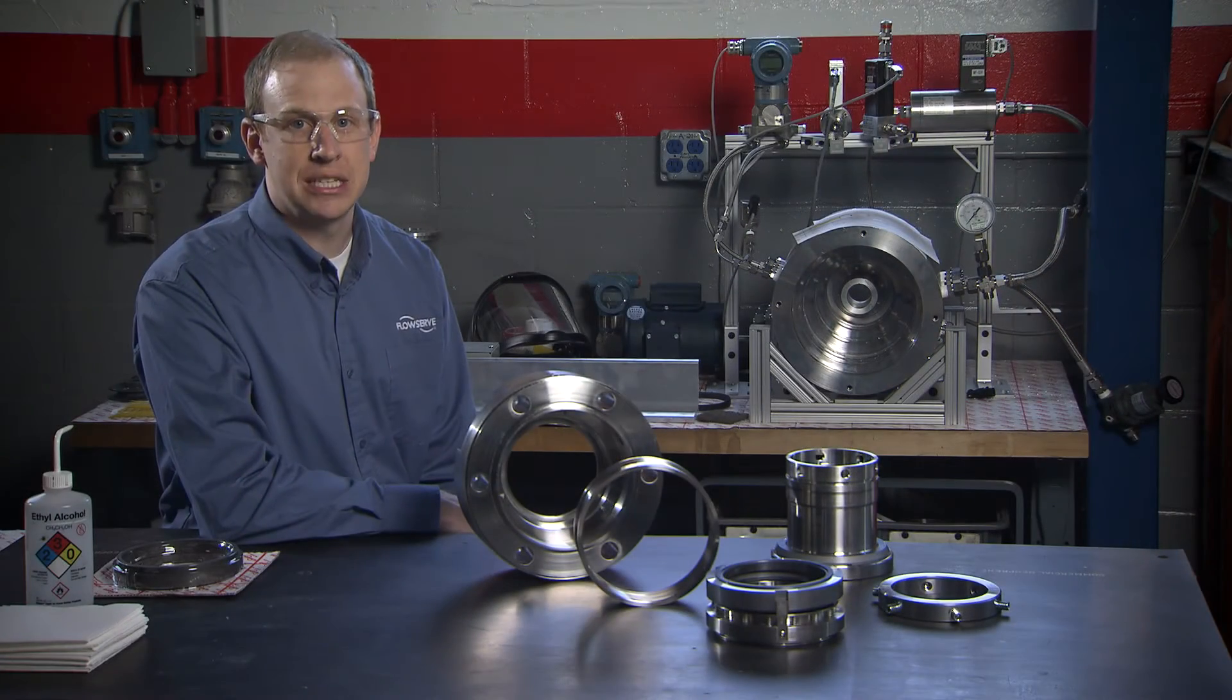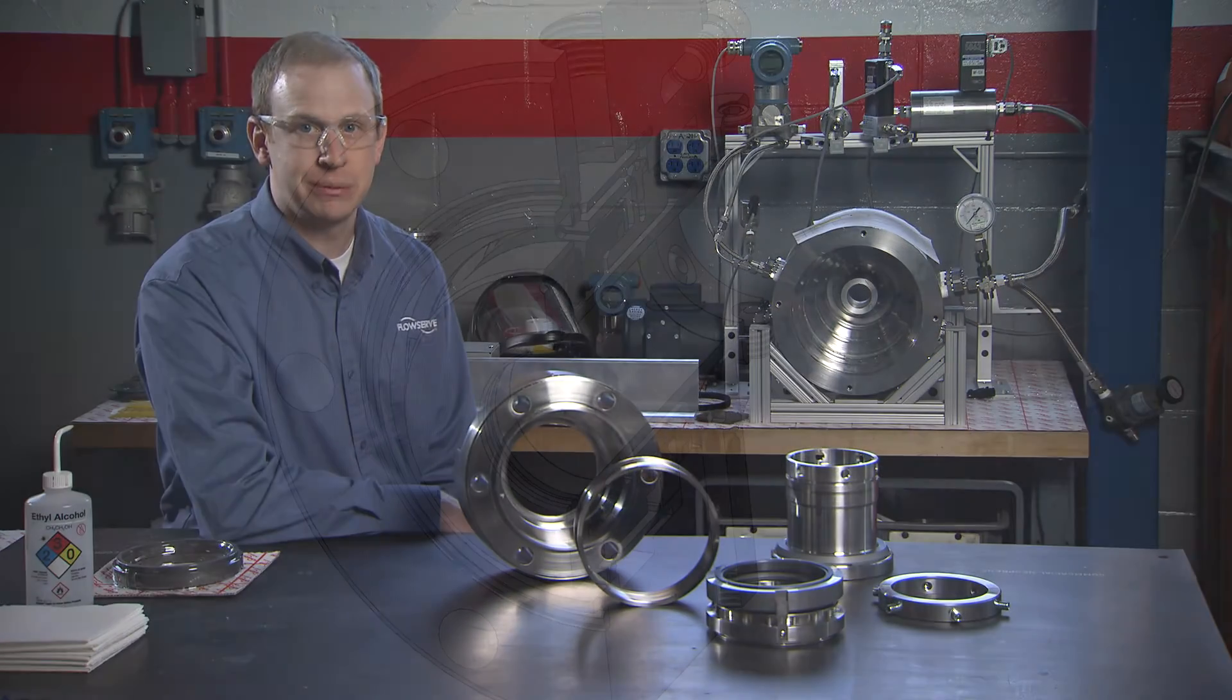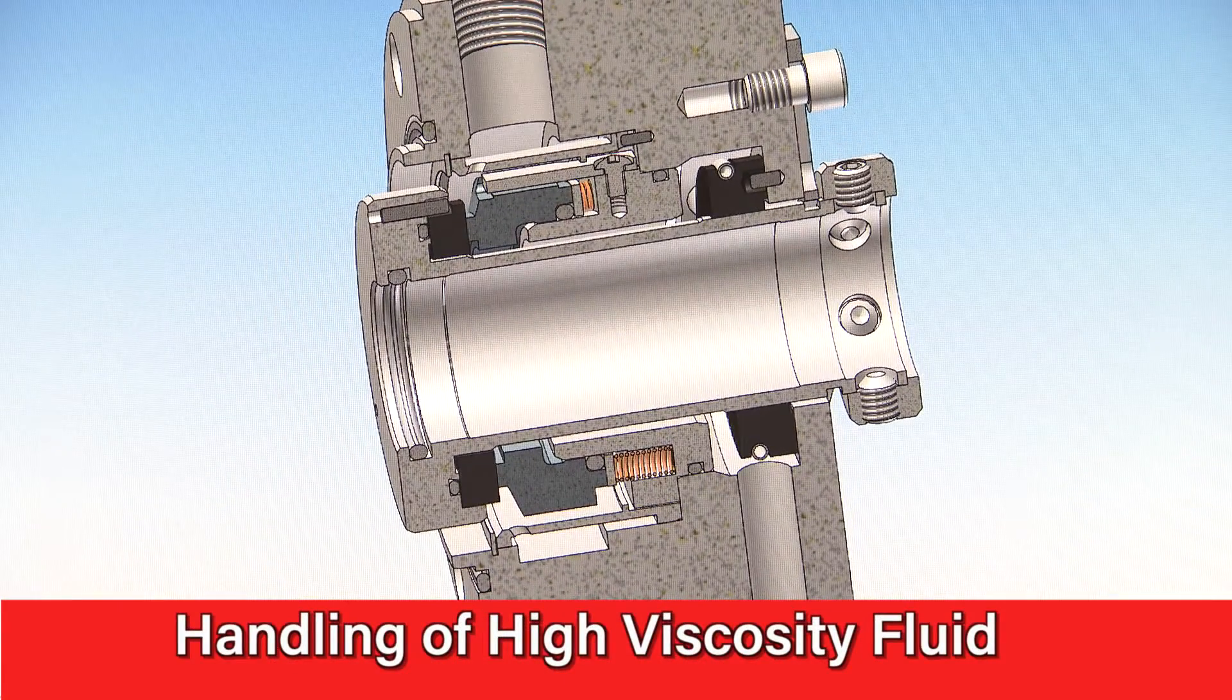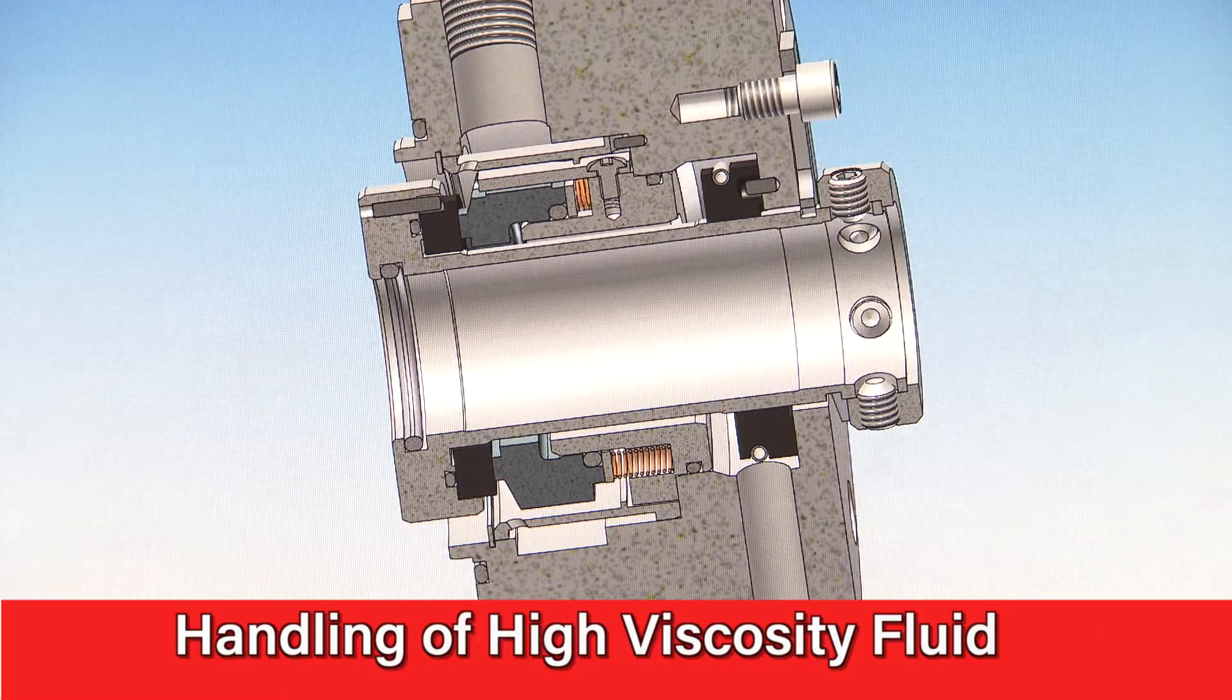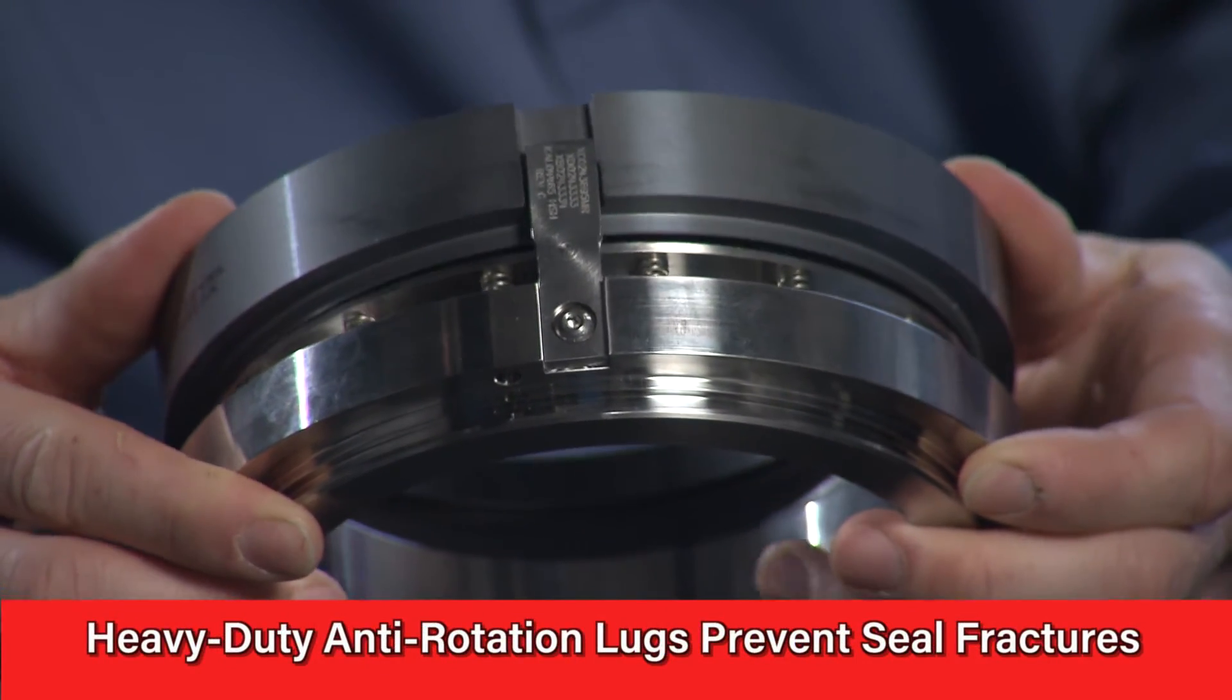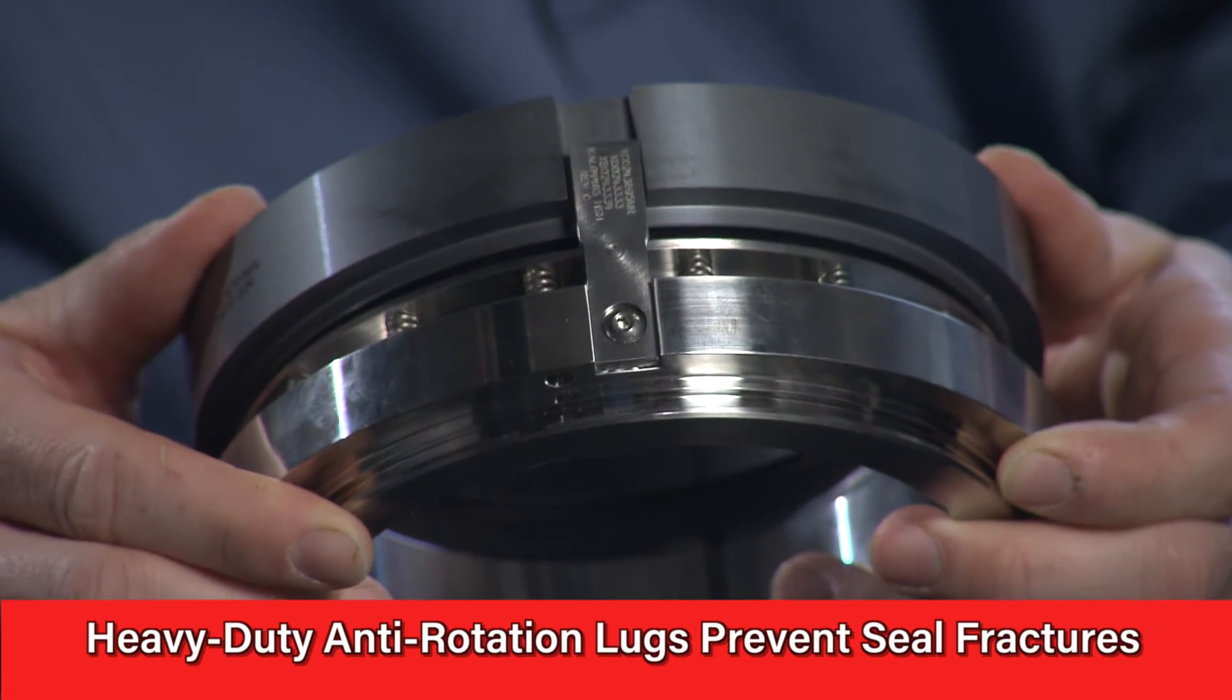Let's take a closer look at some of the seal's more notable features. Handling high viscosity fluid was a primary consideration in the seal design. Heavy-duty anti-rotation lugs engage in the stationary face to prevent seal face fractures or distortions.